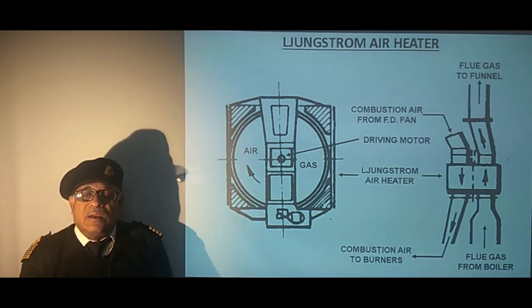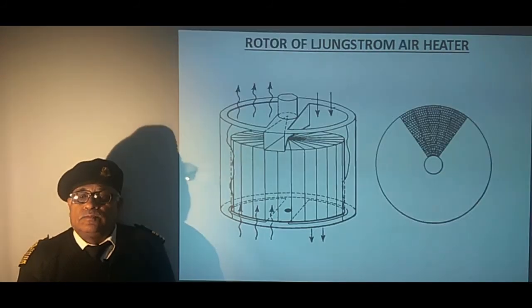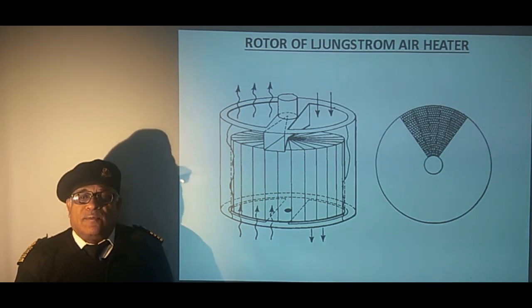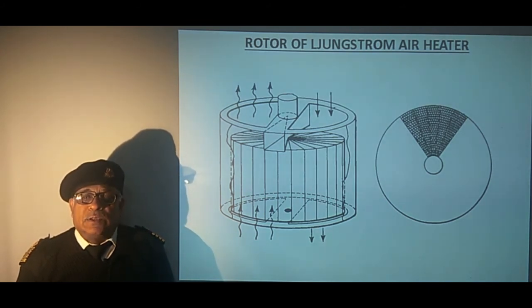The following slide shows the drum internal arrangement. The drum consists of close pitch thin plates which provide large surface area for heat exchange to take place. The plates absorb heat while passing through the flue gas stream and give up this heat when it moves to the combustion air passage. Fine clearance between the stationary and the moving parts limit the mixing of two fluids. So we can see the nomenclature.